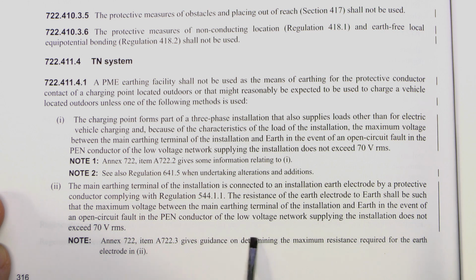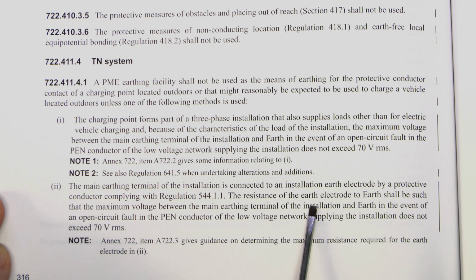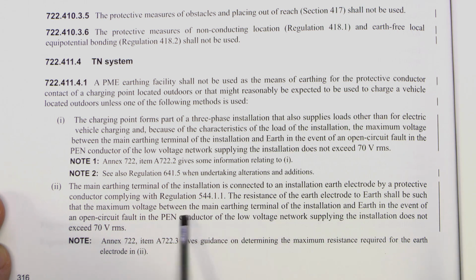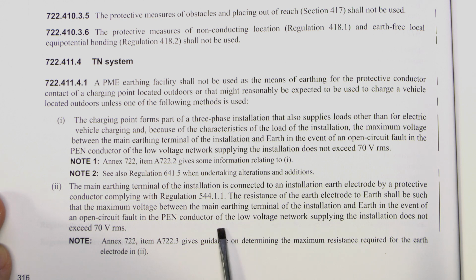Now that's theoretically possible, but to ensure that it doesn't go above 70 volts, the actual impedance of this earth electrode has to be extremely low, and in reality you're not going to be just sticking a rod in the ground and hoping. It's going to have to be a much larger installation with multiple electrodes or some kind of mesh or grid in the ground, that kind of thing. So again, that's not really going to be applicable at a domestic location because it's going to be completely impractical to install that kind of thing.